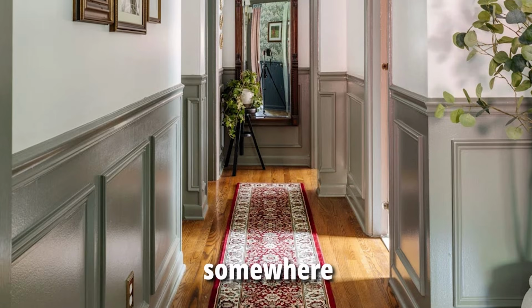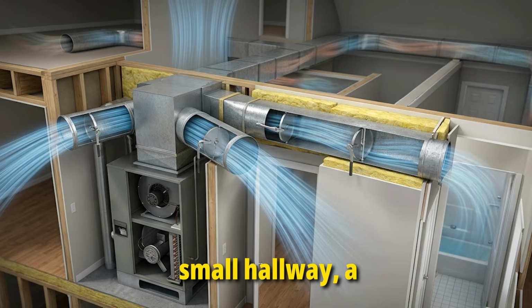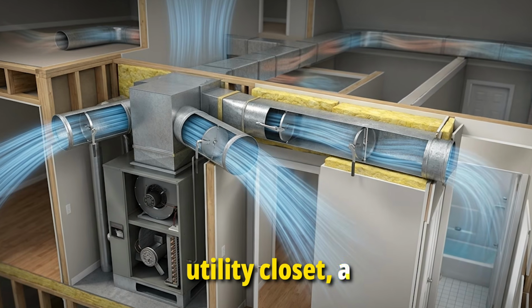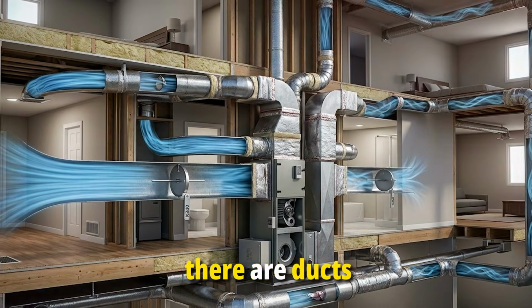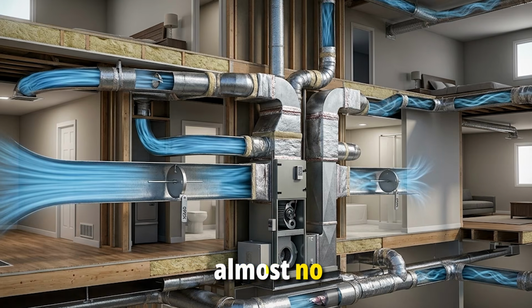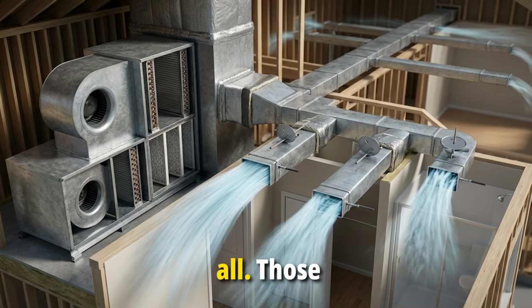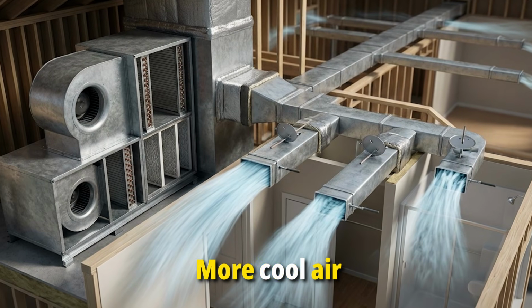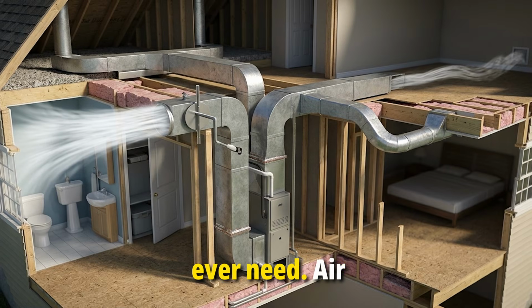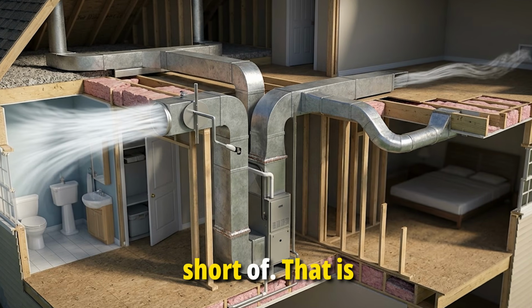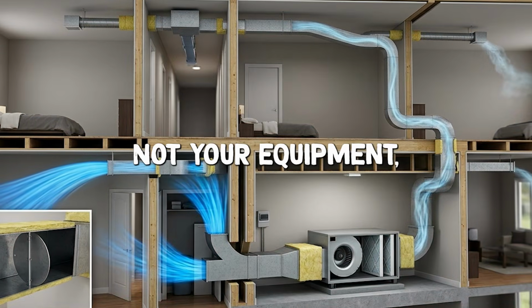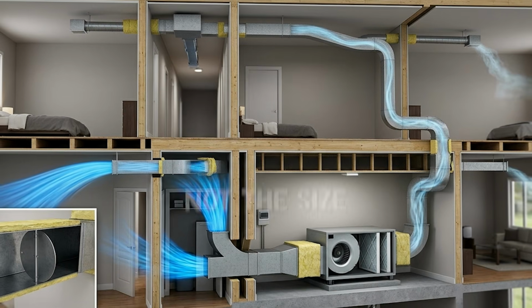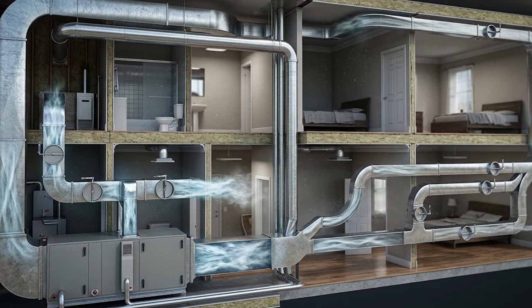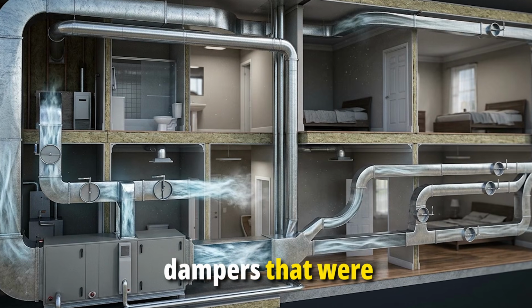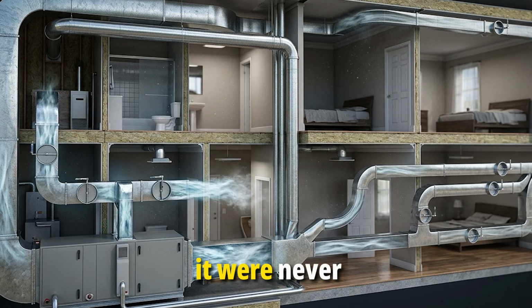Meanwhile, somewhere in your house, a small hallway, a room next to the utility closet, a bathroom near the air handler, there are ducts that run short and straight, with almost no pressure drop at all. Those rooms are getting blasted, more cool air than they will ever need. Air that your far rooms are desperately short of. That is the problem. Not your equipment, not your refrigerant level, not the size of your unit. The airflow was never balanced, and the dampers that were installed specifically to balance it were never touched.